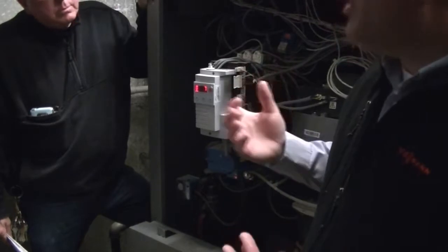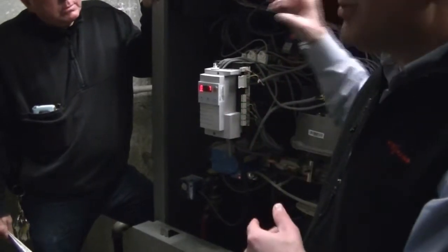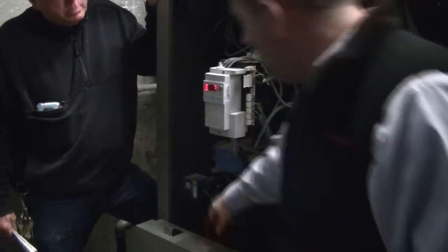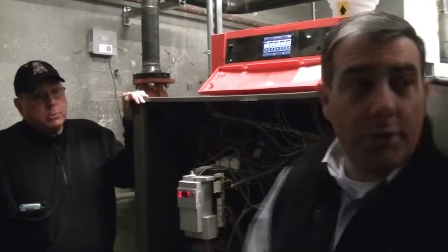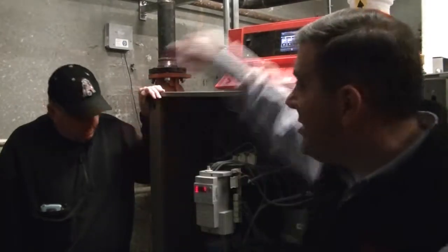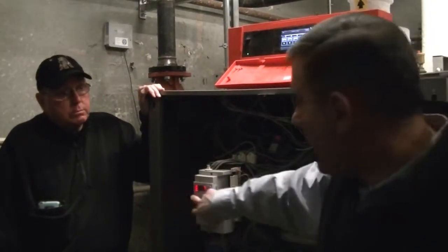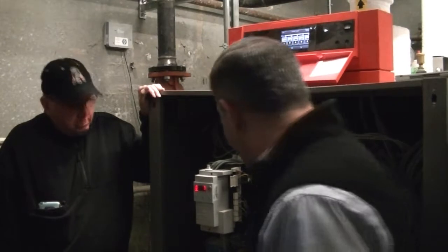If you have a low pressure situation, you'll have a fault that shows up that tells you external safety. Here's your low pressure switch. It's a manual reset low pressure switch. It's just pushing it in if you think you have a low pressure issue. The other thing that could cause that same problem is a low water cutoff. There's a reset button on a low water cutoff as well. But both of those will show up as faults on the control itself. Okay? But that's the main thing. You're not going to be able to reset it from up here. You'll have to take that front jacket panel off and hit the reset button there.